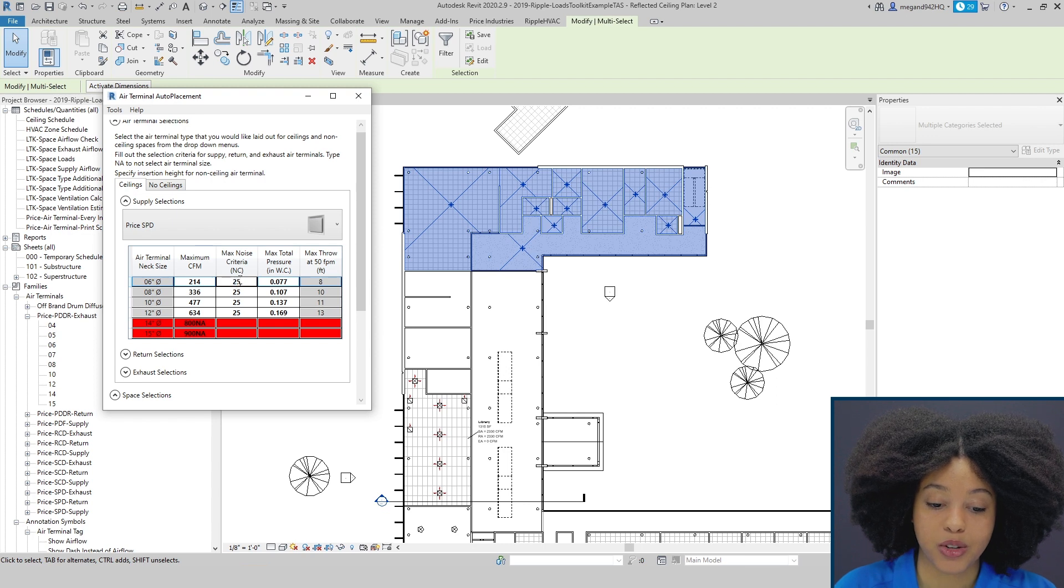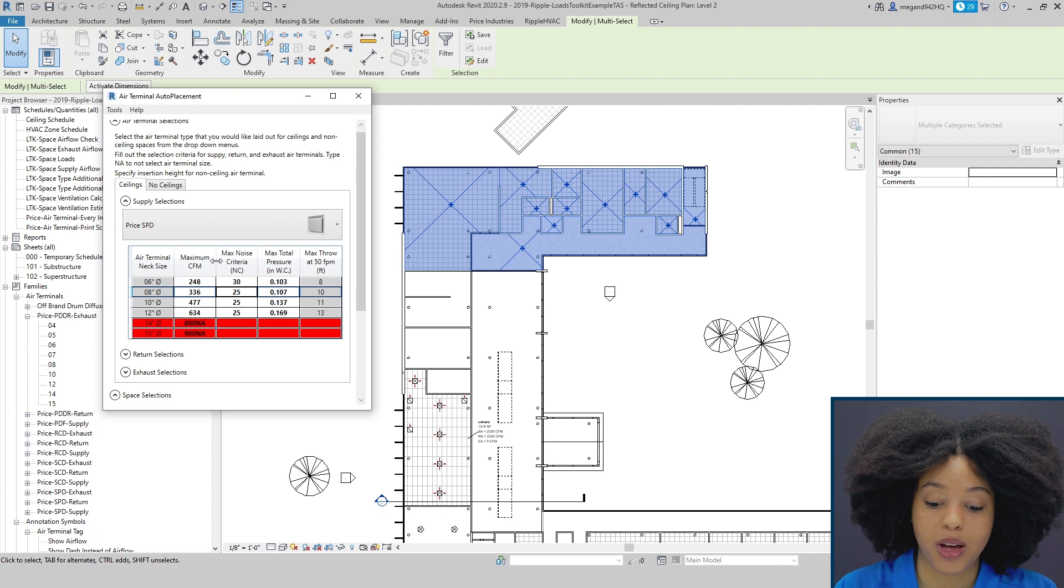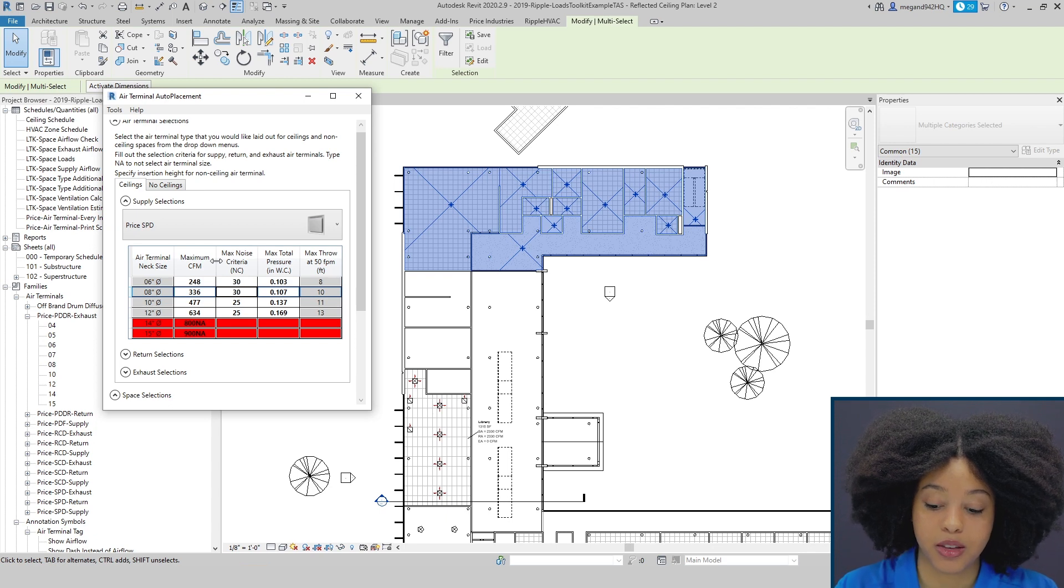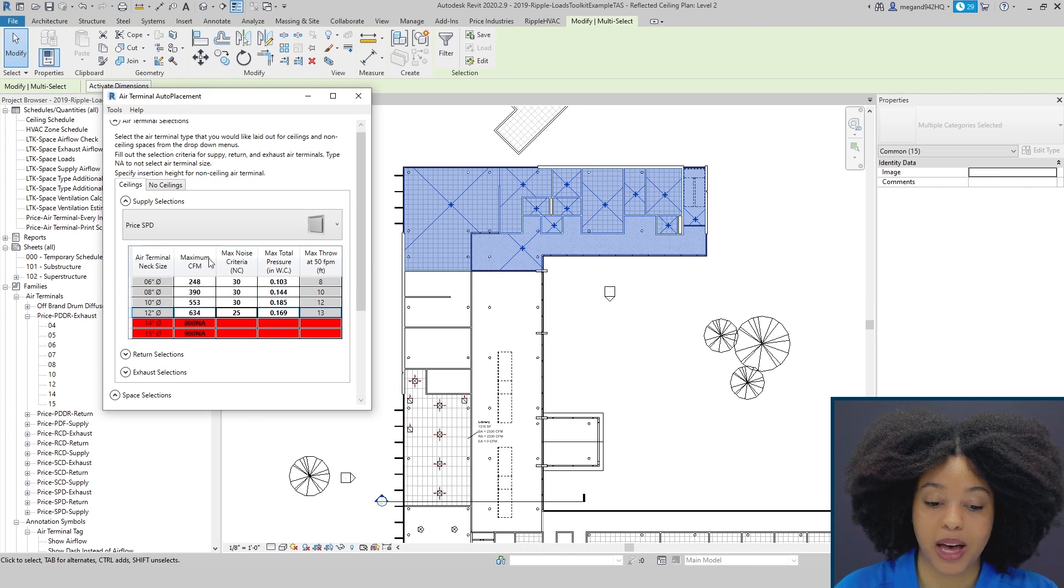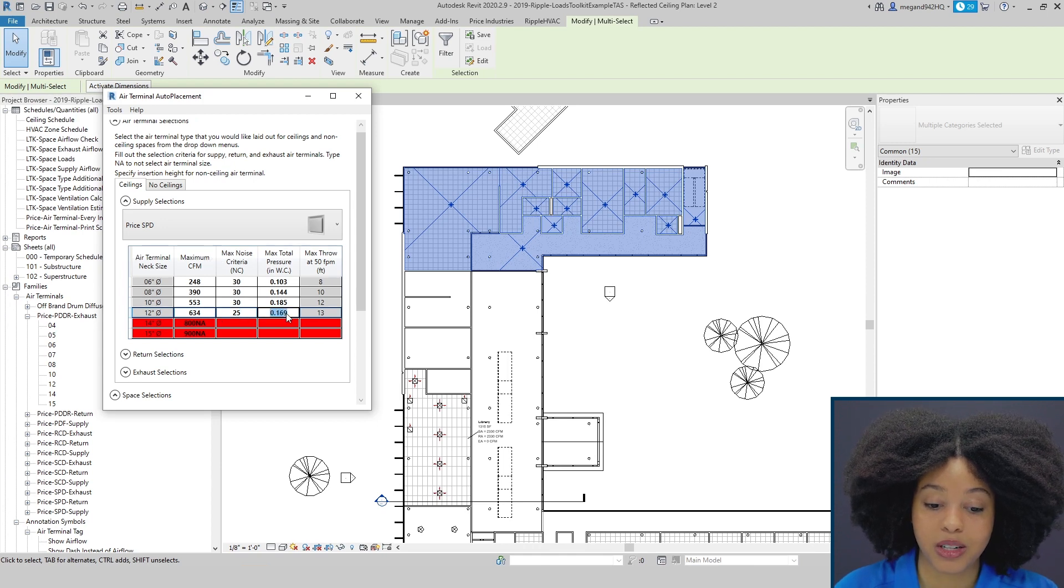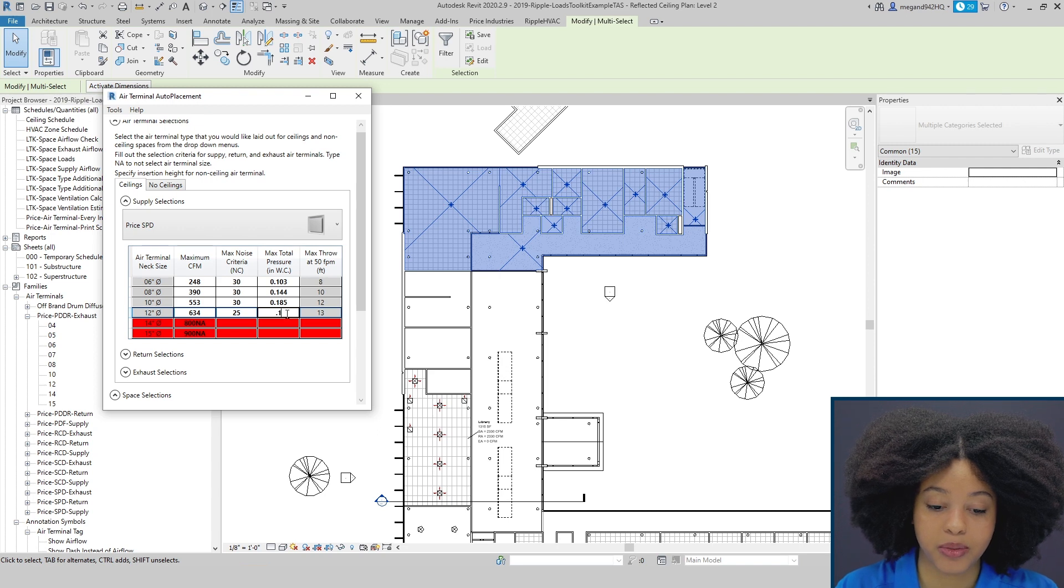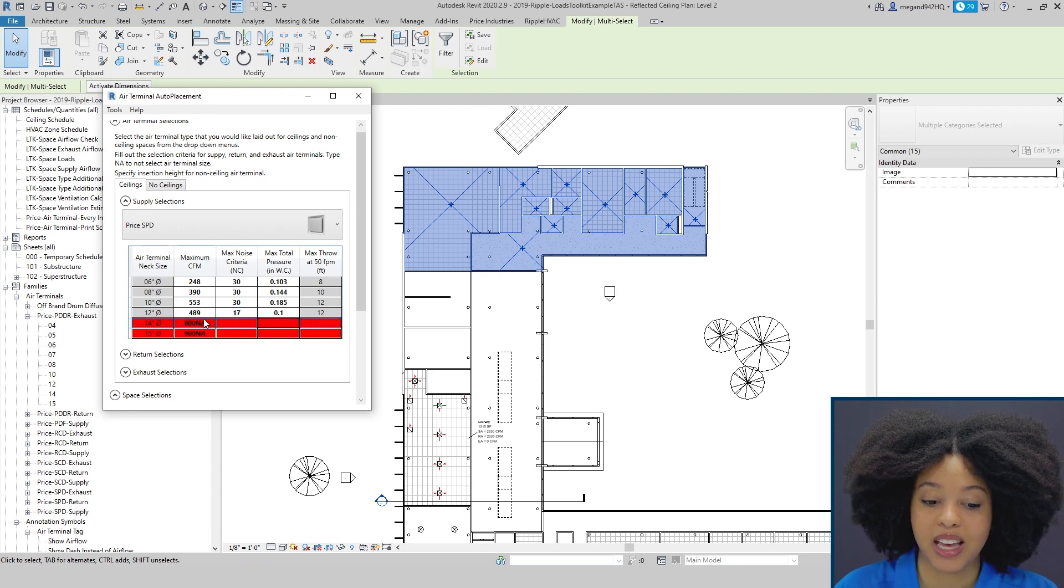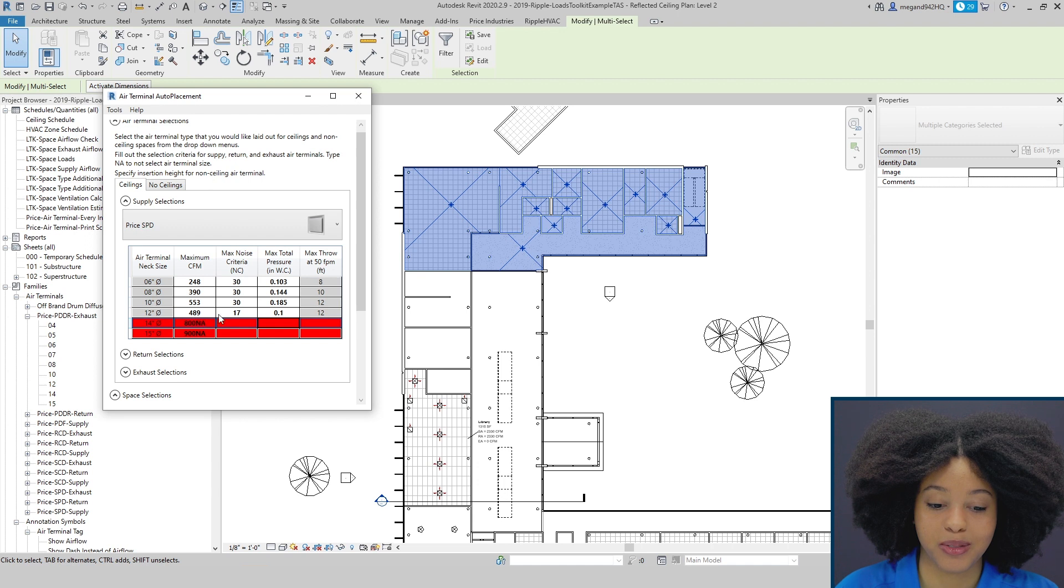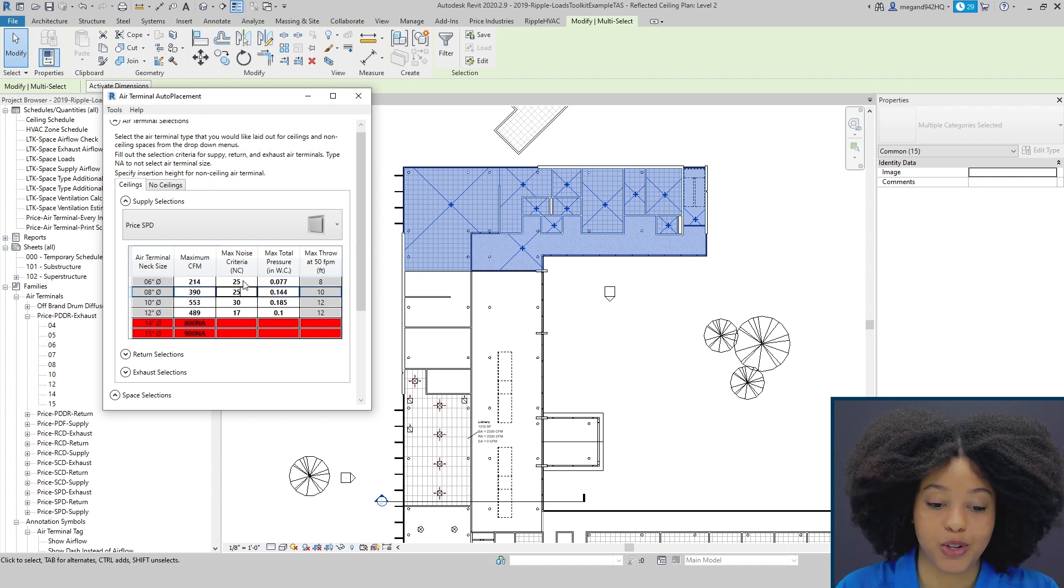For example, if I wanted to specify I don't want any of the diffusers to exceed 30 NC, you'll notice that the other values are back-calculated. Alternatively, we could also specify the max total pressure, and you see it adjusts the other values. For demo purposes, I'm going to keep it to 25 NC.